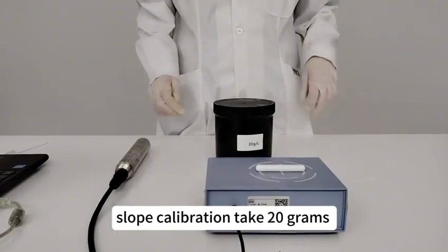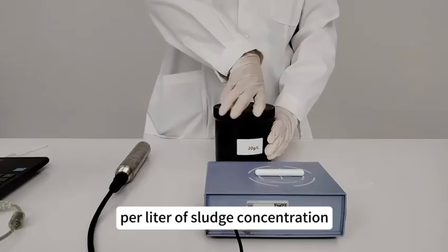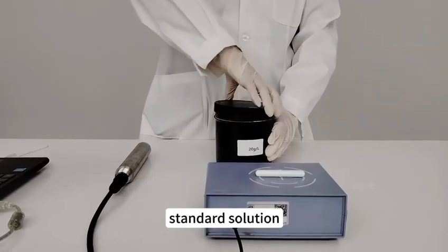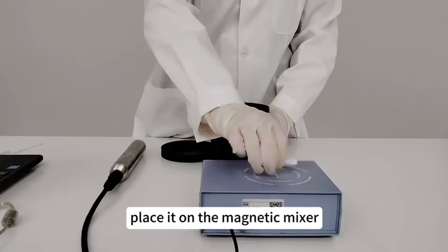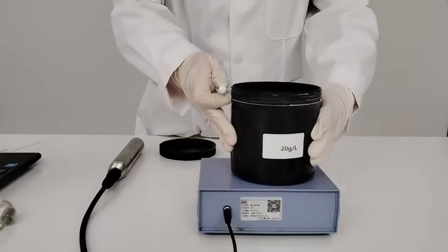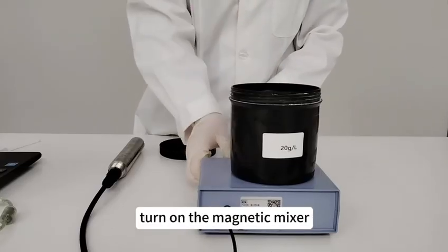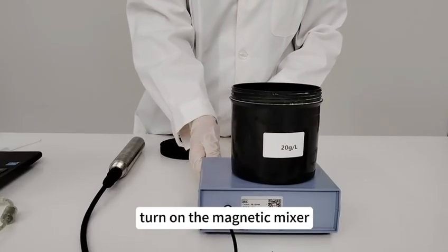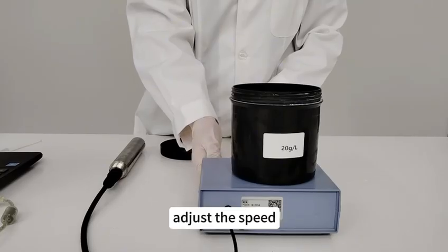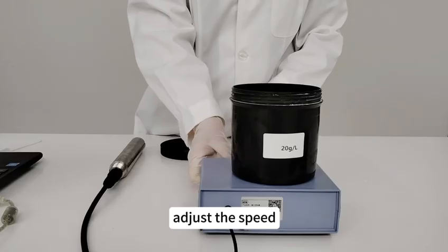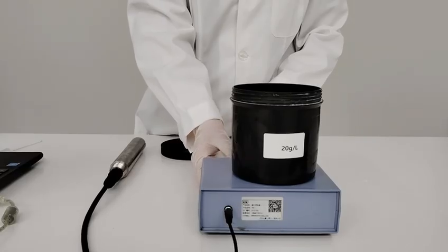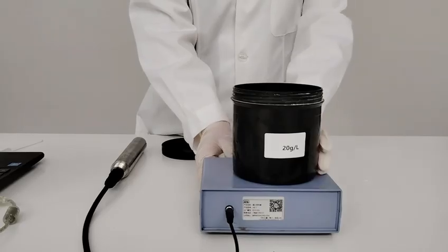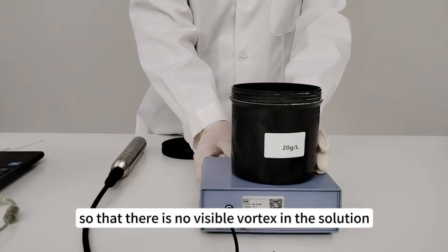Slope calibration. Take 20 grams per liter of sludge concentration standard solution. Place it on the magnetic stirrer. Add the rotor. Turn on the magnetic stirrer. Adjust the speed so that there is no visible vortex in the solution.